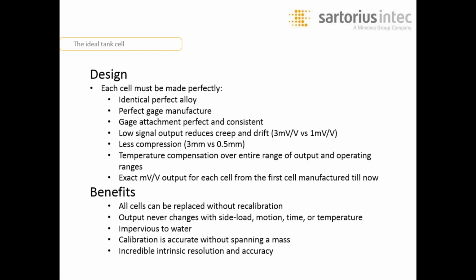Design. When it comes to the canister load cells, each cell must be made perfectly identical: perfect alloy, perfect gauge manufacture. Gauge attachment is perfect and consistent. Low signal output reduces creep. It's got a very small millivolt per volt signal, 1 millivolt versus 3. Less compression. The cell will only deflect 0.5 millimeter at full scale.